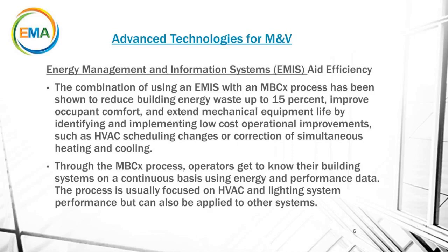The combination of using an EMIS with a monitored-based commissioning process, MBCx, has been shown to reduce building energy waste by up to 15% alone. The fact that you can identify it, monitor it, measure it, and have an alarm or flag to know when a device is out of spec or outside the expected range of energy usage means you can make an impacting change to get back into the efficient range.